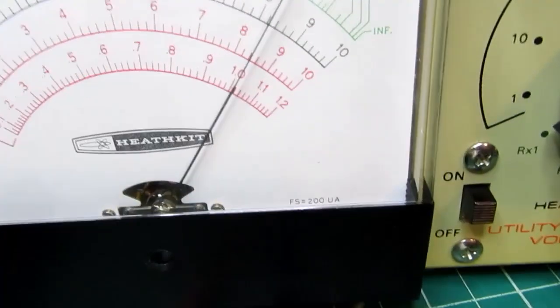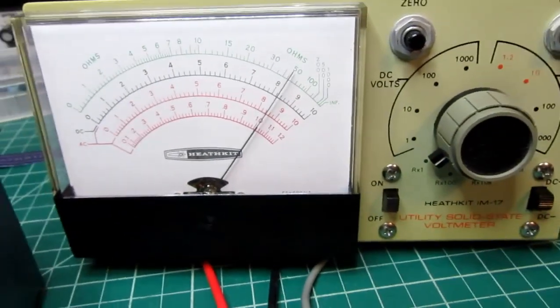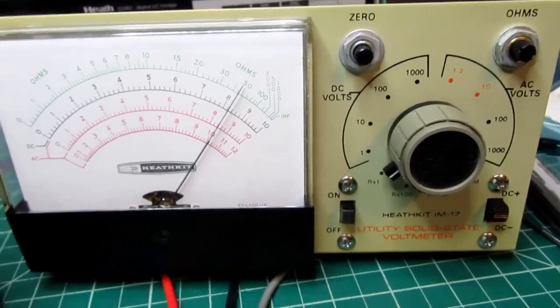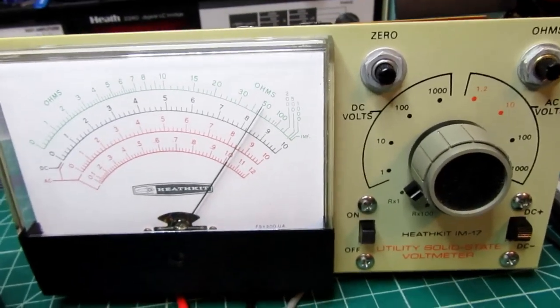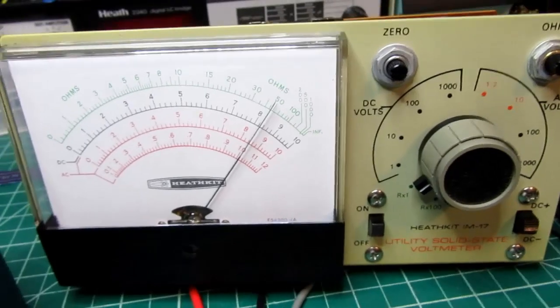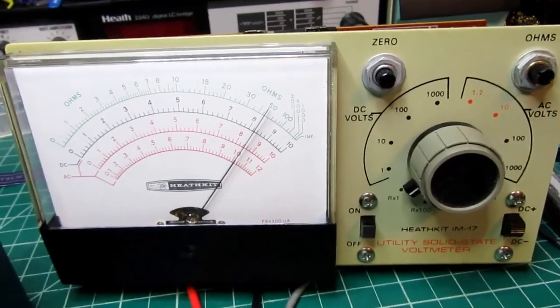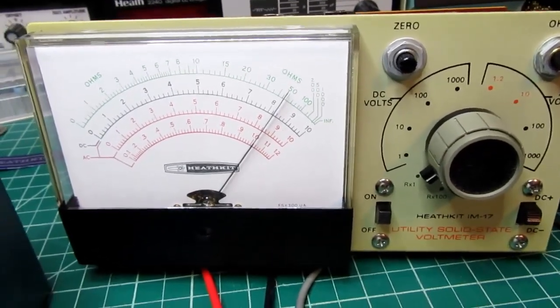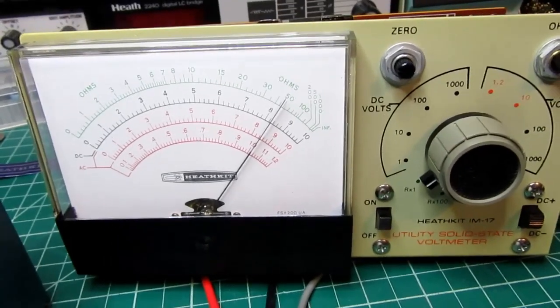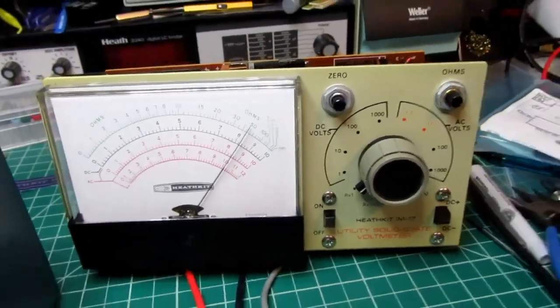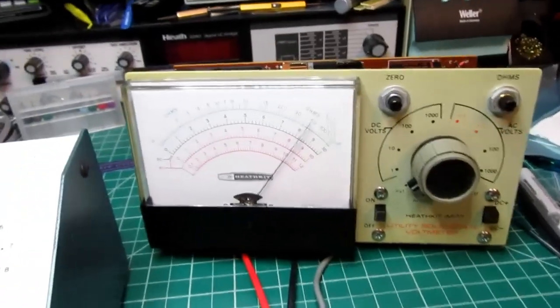It's reading about 50 when it should be reading 60, but again, there's no adjustment on this for that. You just have to go with it. It's resistor tolerances and so on inside the meter. Can't do much about it without replacing everything. And even then, the specifications are so poor that all you're trying to do is get in the ballpark with this. You can't really hope for better.